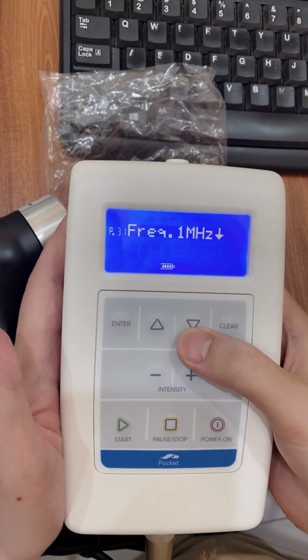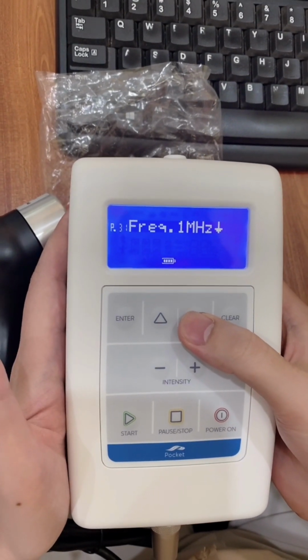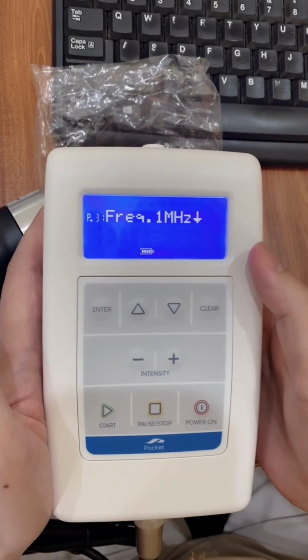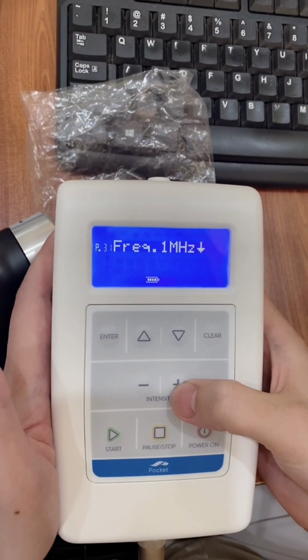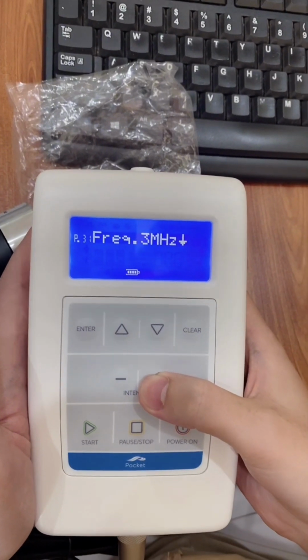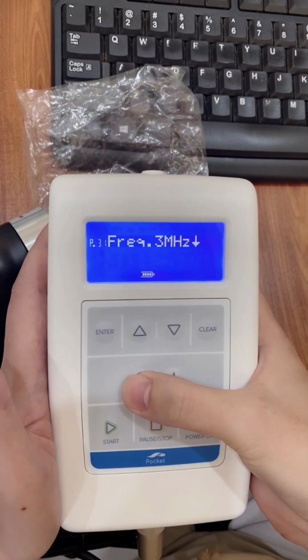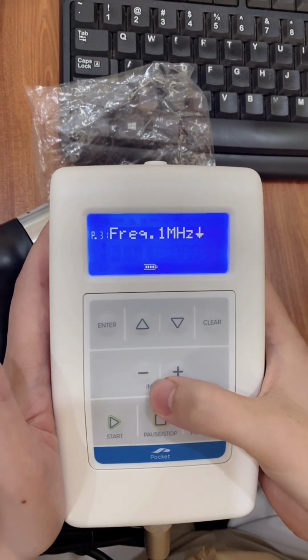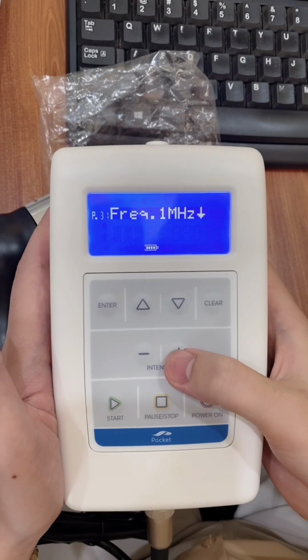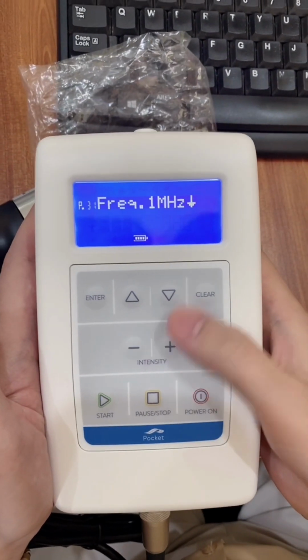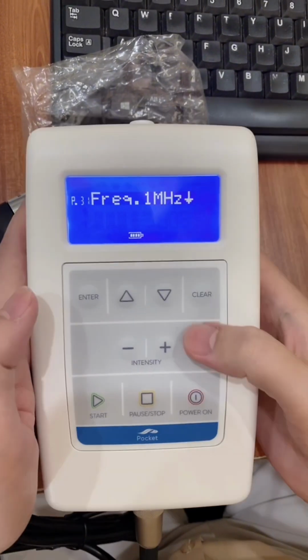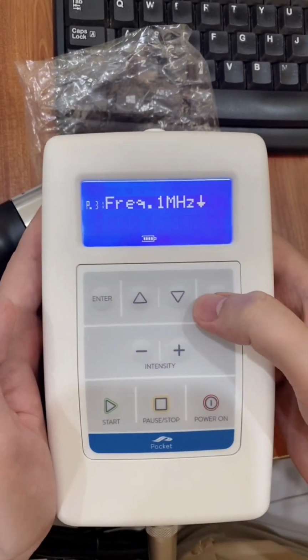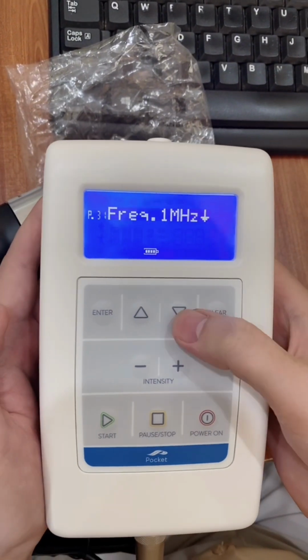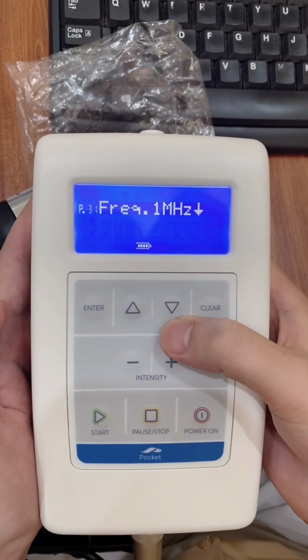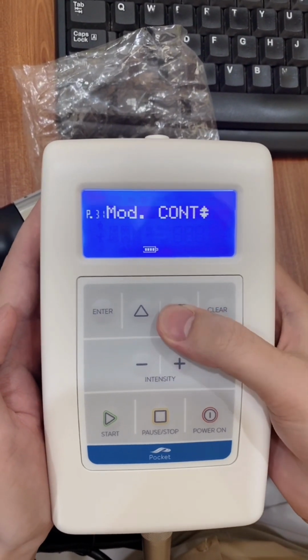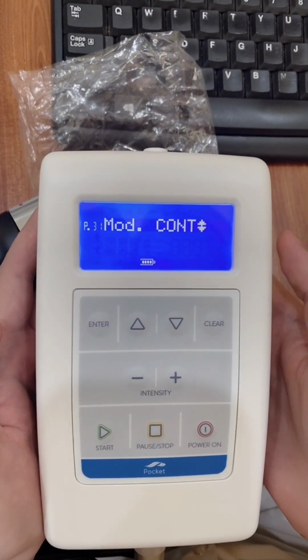Here you can see the parameters that you can adjust. The first parameter we can see here is the frequency. You can choose between 1 megahertz or 3 megahertz. For me, the frequency of 1 megahertz will bring the best result for you. So please select this one. And you can use the up and down button to select among the parameters to set up. Here's the frequency. This is the working mode.